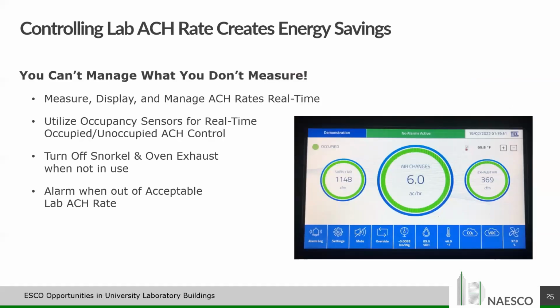Now, all these different items of the lab space are necessary to be able to control, as Paul mentioned, air change rates through our room space controller. So what we're doing here is basically one of these iPad-type looking controllers gets mounted on the screen or on the entrance of the lab, and basically provides you real time, real information on what's happening in your lab space, controlling to either 6 air changes or 8 air changes or 4 air changes unoccupied. And basically what we're doing is we're controlling that to that number, depending whether your snorkels are on or off, or your fume hood sash is lifted or closed, and basically maintaining that optimal level of 6 air changes per hour, regardless of what's happening in that lab space.